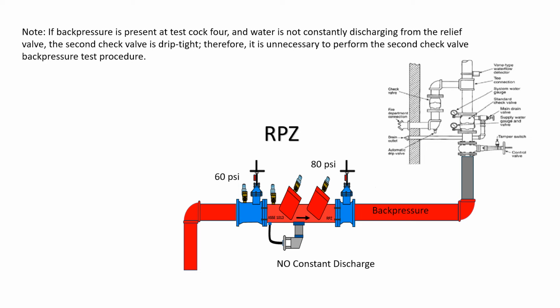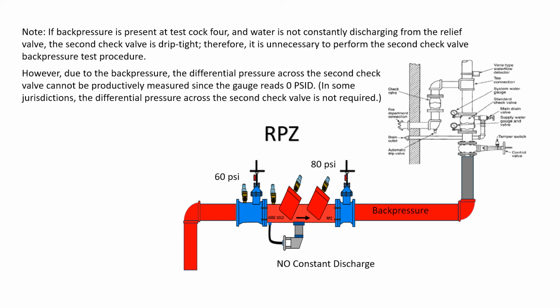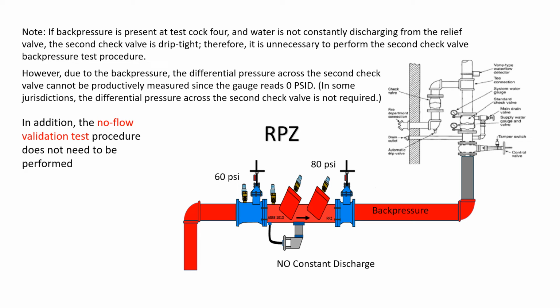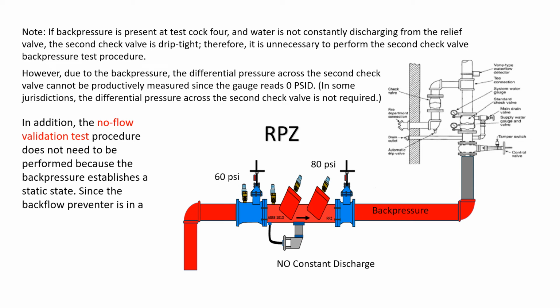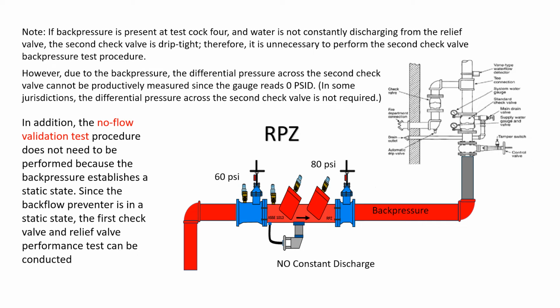Therefore, it is unnecessary to perform the second check valve backpressure test procedure. However, due to the backpressure, the differential pressure across the second check valve cannot be productively measured, since the gauge reads 0 psid. In some jurisdictions, the differential pressure across the second check valve is not required. In addition, the no-flow validation test procedure does not need to be performed, because the backpressure establishes a static state. Since the backflow preventer is in a static state, the first check valve and relief valve performance test can be conducted. Proceed to the appropriate procedures.